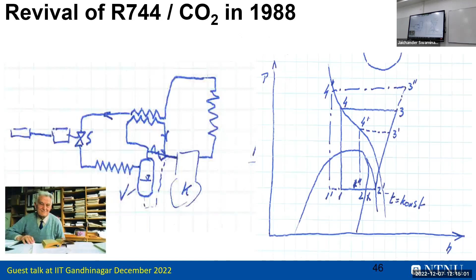Then Gustav Lorentzen said we can use CO2 smartly by adjusting the high side pressure. It's not the valve anymore controlling the superheat - it's just controlling the pressure, how much charge do we move from the low side to the high side. As you see, if the charge is too low, your COP is poor. If it's good, it's perfect. If it's too high, you can get a little bit more, but you pay a lot. So there's always an optimum high side pressure in these processes.